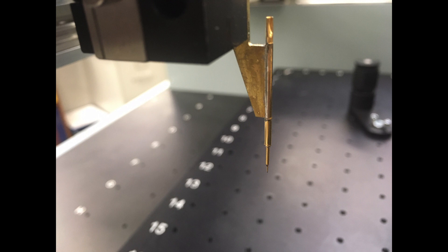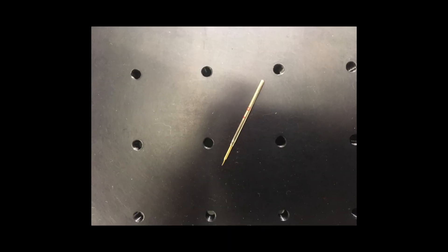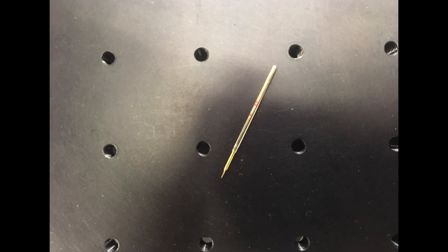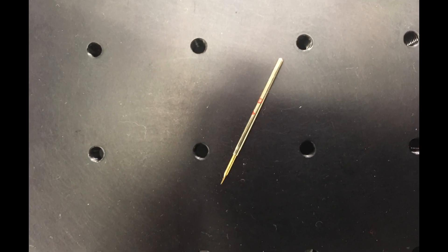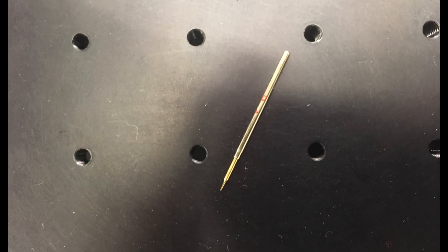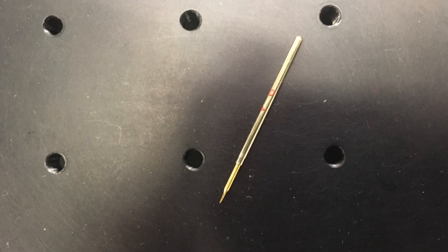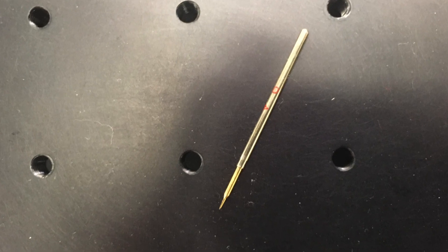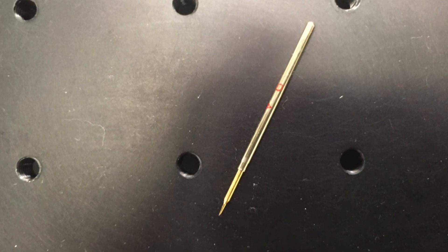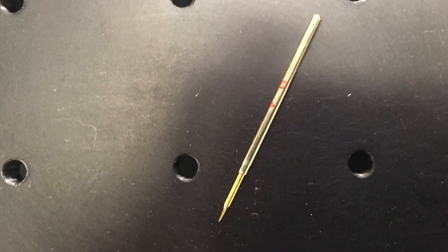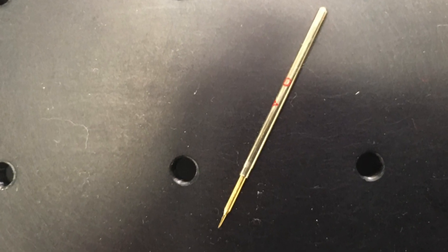The probe Huntron supplies for testing through conformal coating uses a very sharp high spring force needle from QA Technologies. It is effective for most pliable conformal coatings. It is not intended to be used on uncoated PCBs.